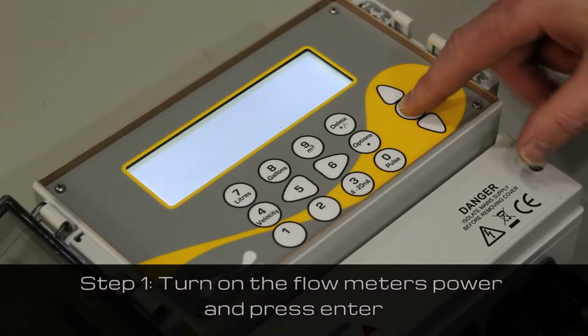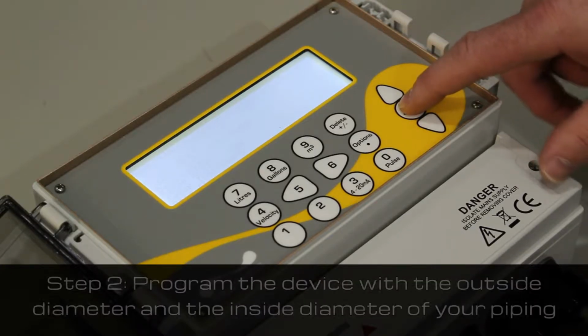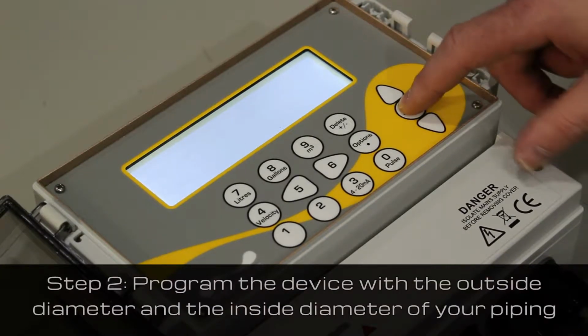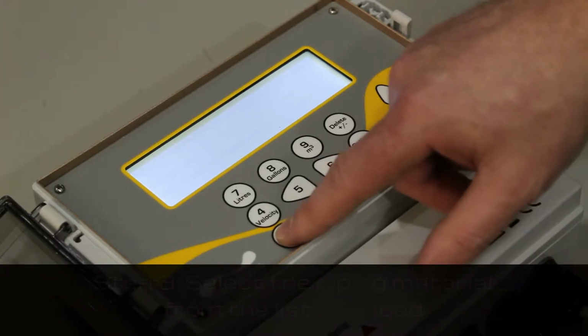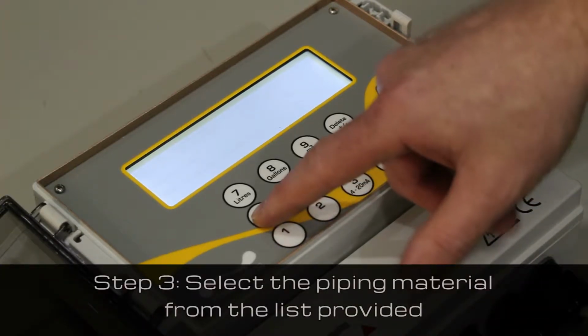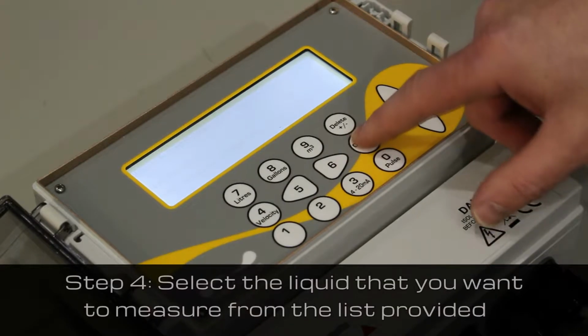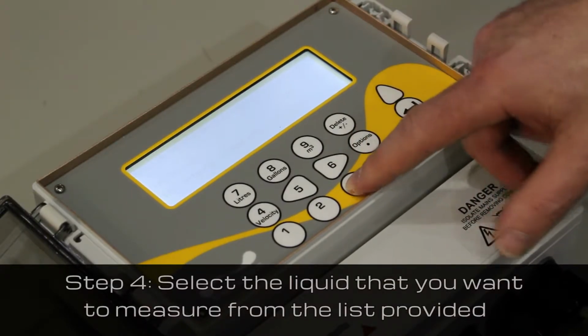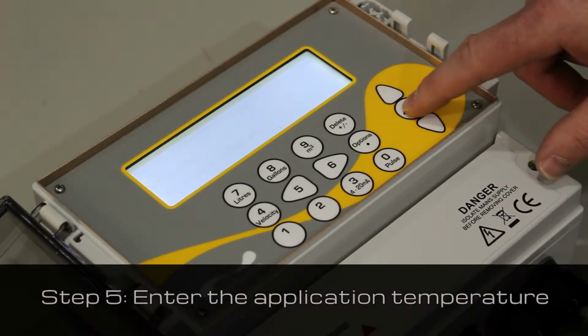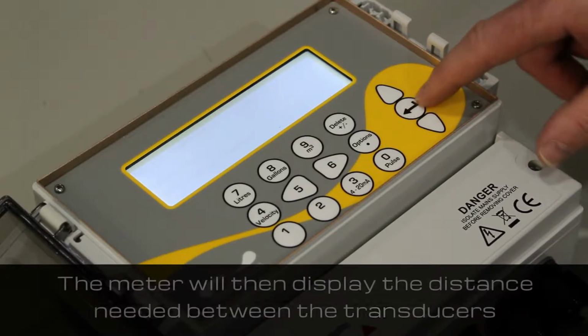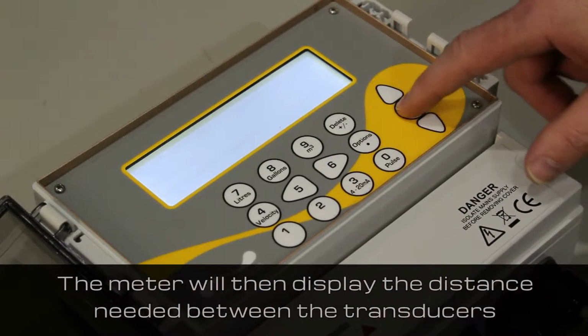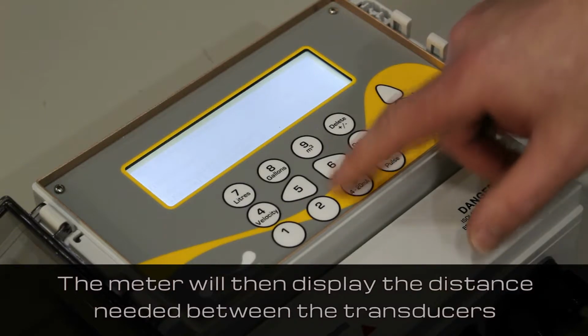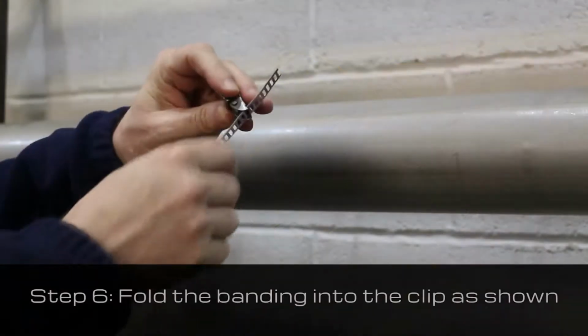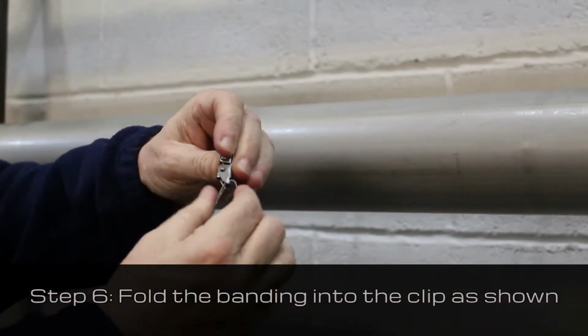To begin, switch the device on and press Enter. You will need to program the device with the outside diameter and the inside diameter of your piping. Then select the piping material from the list provided. Next, select the liquid that you want to measure from the list provided. Enter the application temperature. The meter will then calculate the distance needed between the transducers and will display it on the screen.